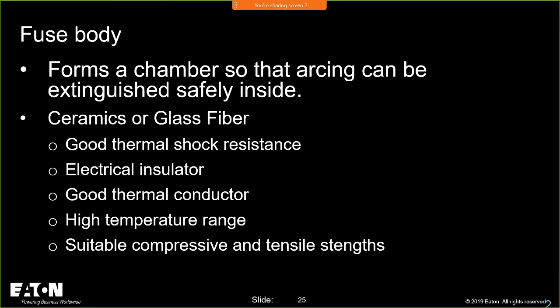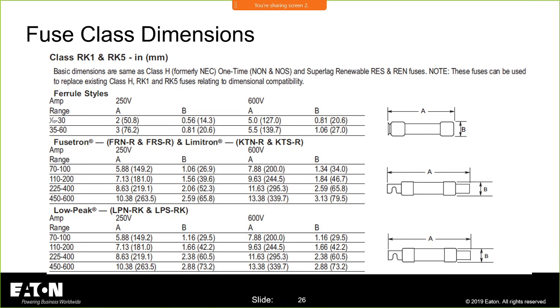So I know in the early days, the fuse element was in open air. As they tried to interrupt higher voltages and higher currents, they had to basically restrict that. And then the size of the fuse is driven by the class of the fuse. In the way we list these devices, there will be specific dimensions governed by the UL standards that tell us when we make this specific class fuse, it has to be a certain size, and you'll have the dimensions of the length, the width, and all that good stuff. Remember, we had a standard for the fuse and we had a standard for the holders. So there will be different dimensions for each different fuse.